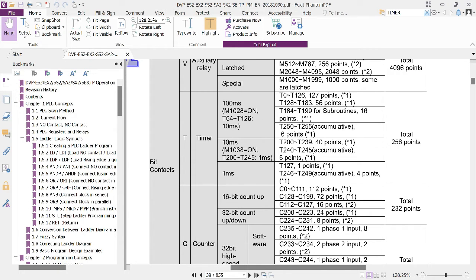These are the timers supported by a Delta PLC — they've got ranges. This region here is under a 100 millisecond time base. T0 to T126 gives us 127 timers under the 100 millisecond time base. Then from T250 to T255 we have accumulative timers under a 100 millisecond time base — meaning when the PLC stops or power switches off, when you switch on again it starts accumulating from where it left off rather than resetting to zero.